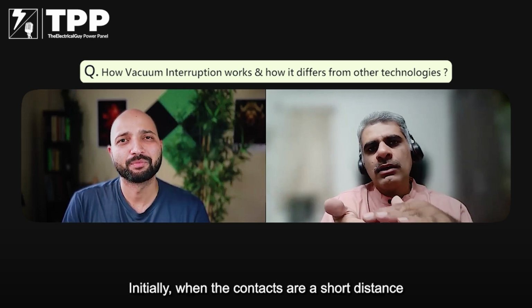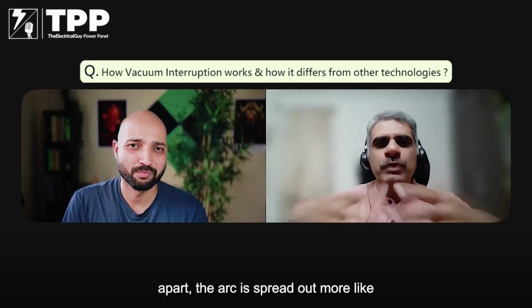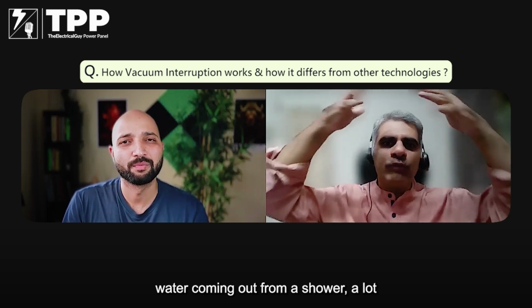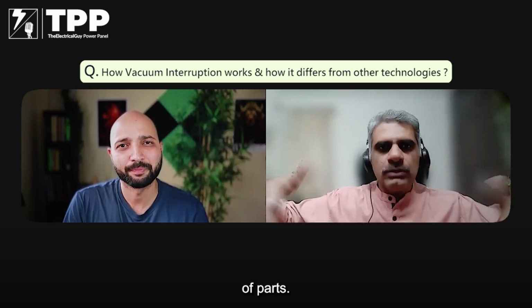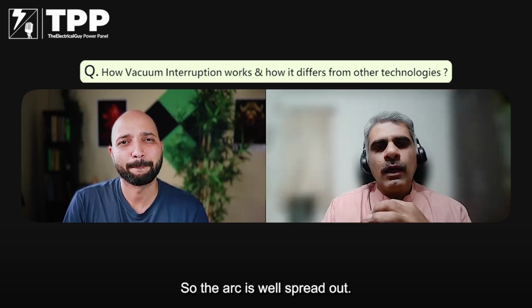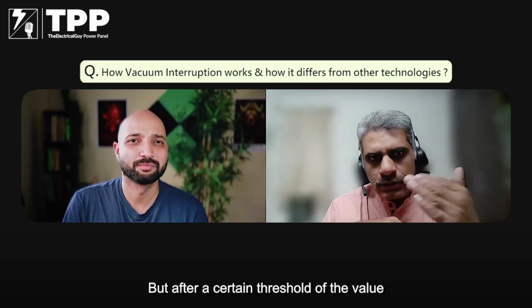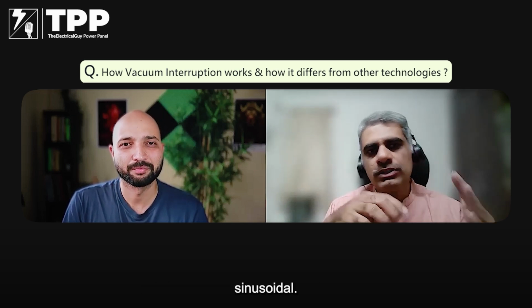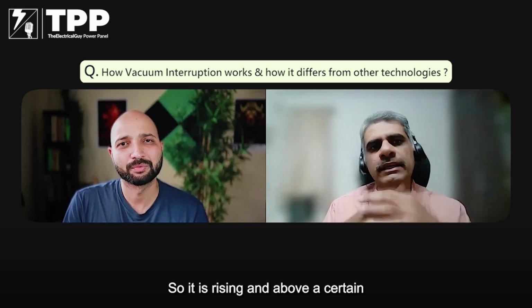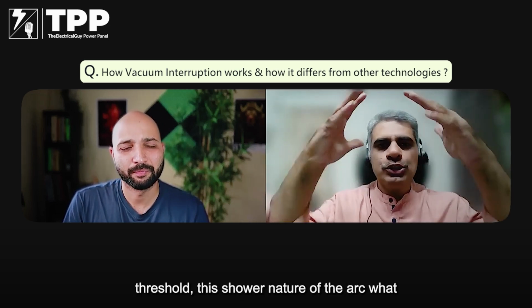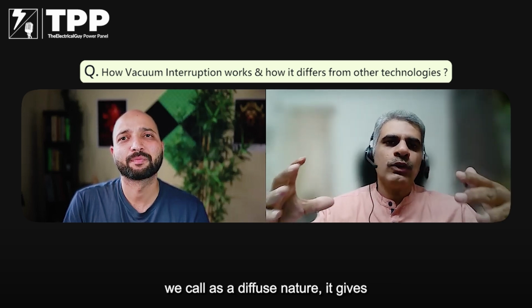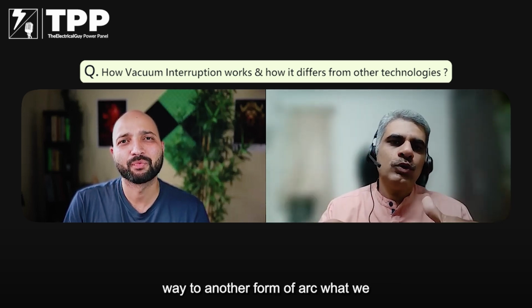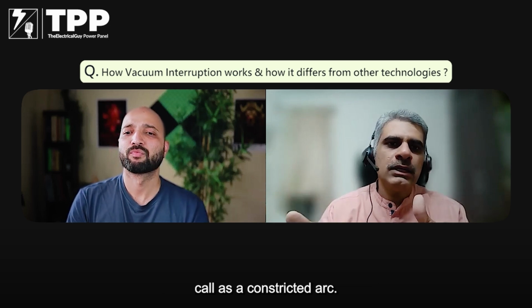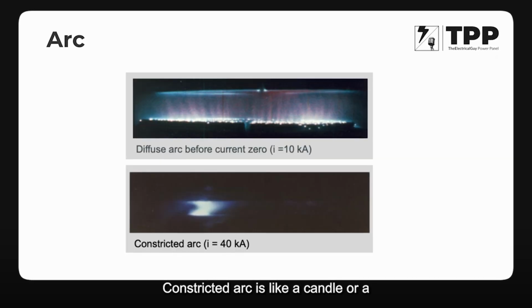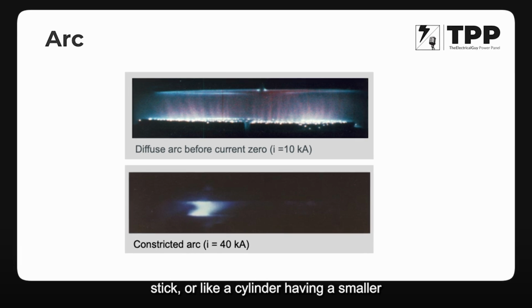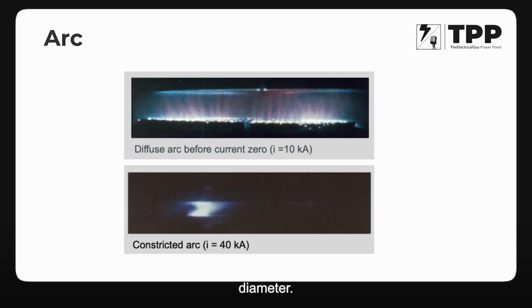Initially, when the contacts are a short distance apart, the arc is spread out, more like water coming out from a shower, with a lot of paths. So the arc is well spread out. But after a certain threshold of the value of current, because as we know, current is sinusoidal, so it is rising, above a certain threshold this shower nature of the arc, what we call a diffuse nature, gives way to another form of arc, what we call a constricted arc. A constricted arc is like a candle or a stick, or like a cylinder having a smaller diameter.